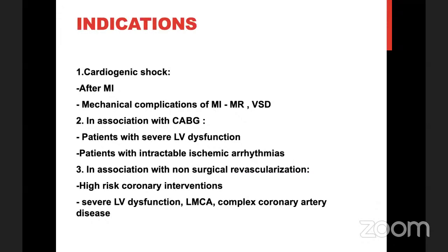Indications for the balloon pump are cardiogenic shock, as we mentioned in the previous slides, after MI or mechanical complications of MI, MR or VSD, in association with CABG, patients with severe LV dysfunction, patients with intractable ischemic arrhythmias, or in association with non-surgical revascularization like high-risk coronary interventions, severe LV dysfunction with left main coronary artery disease, and complex coronary artery diseases.